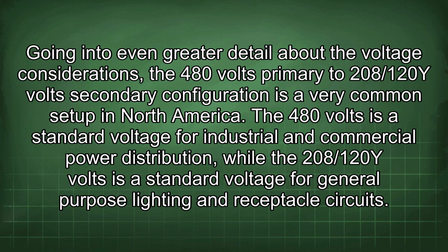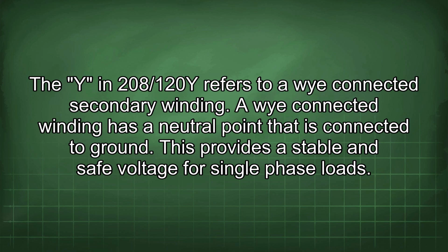The 480 volts is a standard voltage for industrial and commercial power distribution, while the 208/120 volts is a standard voltage for general purpose lighting and receptacle circuits. The Y in 208/120 refers to a Y-connected secondary winding. A Y-connected winding has a neutral point that is connected to ground. This provides a stable and safe voltage for single-phase loads.